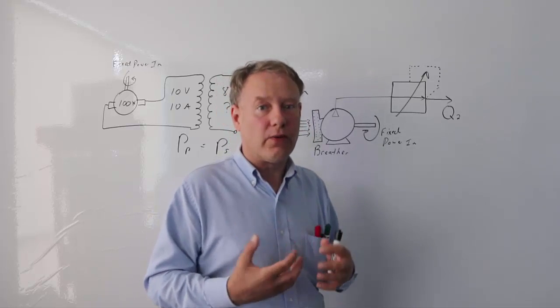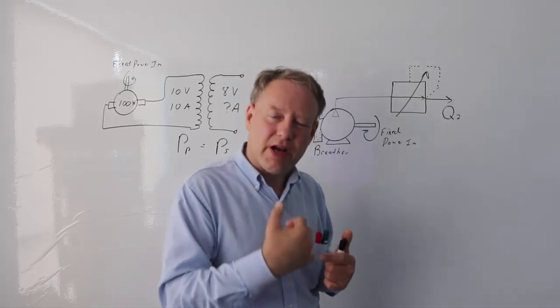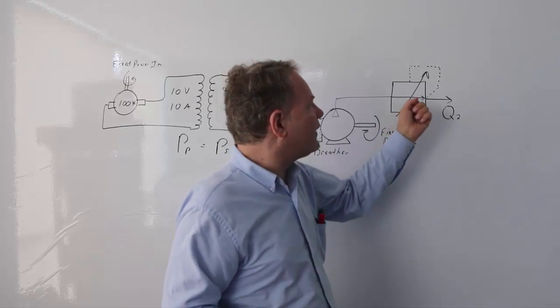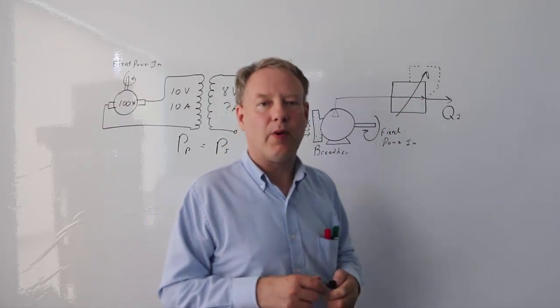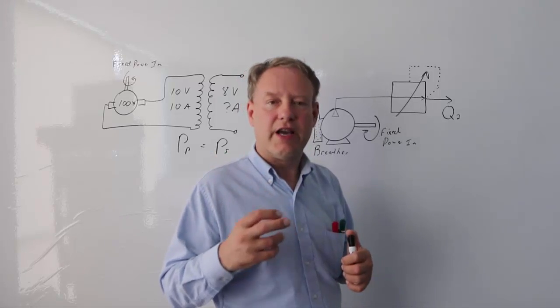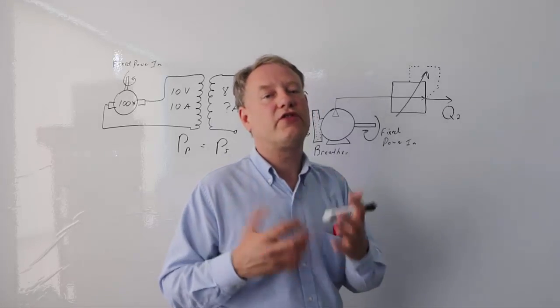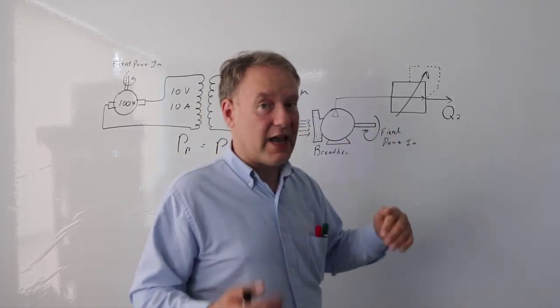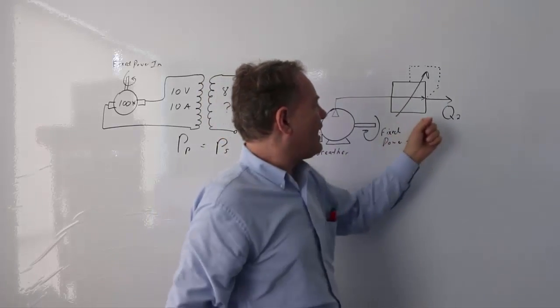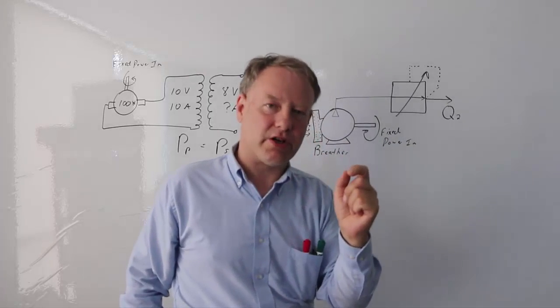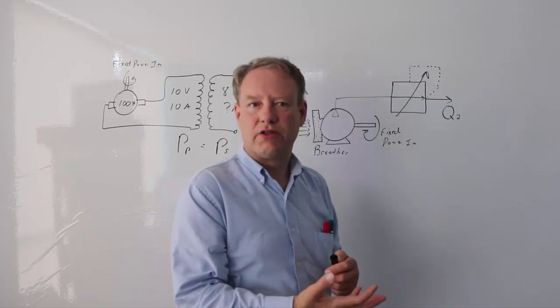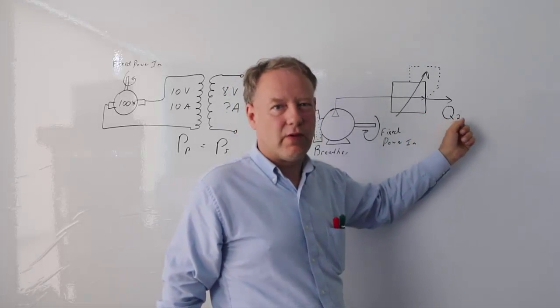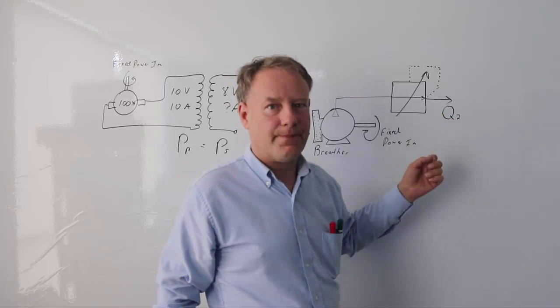When we define the flow rate for all of our actuators, we have to say what pressure is actually running. We also need to know the available pressure from our compressors. The compressor is rated to a CFM linked to a pressure, and often they'll have two different availabilities. So if this says 4 CFM at 90 PSI but we're running at 70 PSI and we need 5 CFM, will it work?